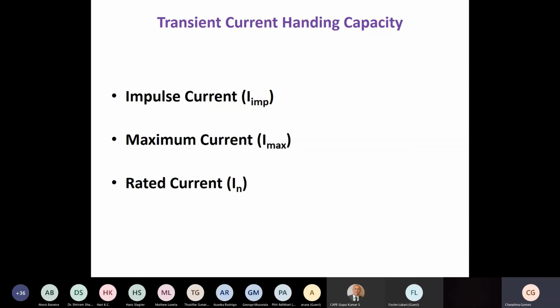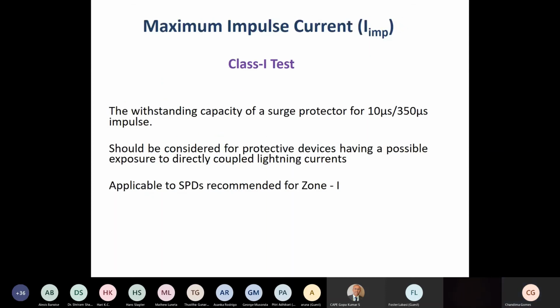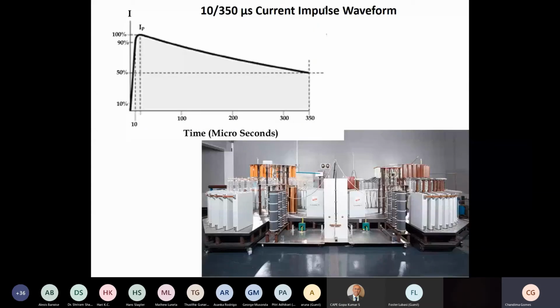Okay, then transient current handling capacity. We have 3 types: impulse current, Imax, maximum current, and rated current. What is impulse current? This is a test specified for zone 1 protectors, which is tested for a current which is named 10 microsecond by 350 microsecond. We call it 10 by 350 waveform. And when that waveform is applied, this is a generator, what you see in the picture below, 10 by 350 current, impulse current generator.